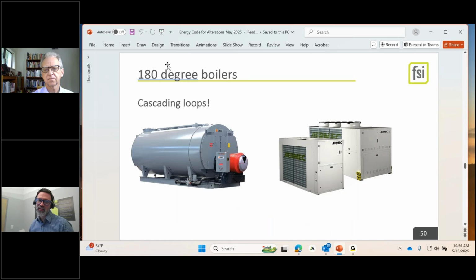Where it doesn't work so well, 180 degree boilers. So right now the only heat pump solution we have are cascading loops, and several people make these. But you basically run an air to water heat pump and then another water to water heat pump to boost that water temperature up to the 180 you can make. And it's not an energy efficient or particularly good solution.